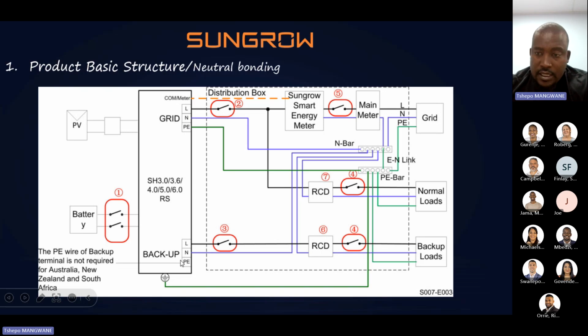I see you have experience of wiring as well. So there is our live and neutral on the backup side. We'll be mainly focusing on neutral in this scenario. If you check here, we have our neutral from the backup port. If we follow it up, it's common with the grid incoming neutral. And also there is a bridge piece between the ground bus bar and the neutral bus bar, or terminal.